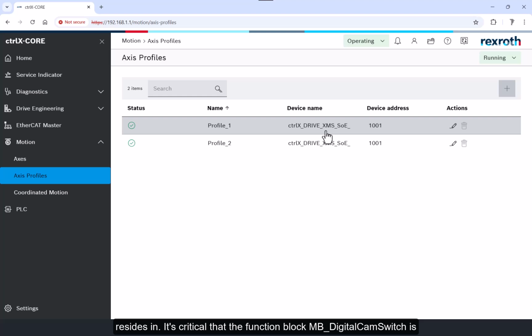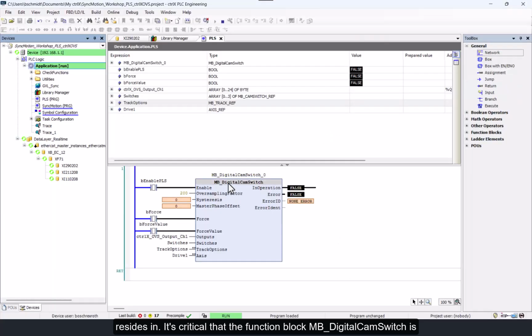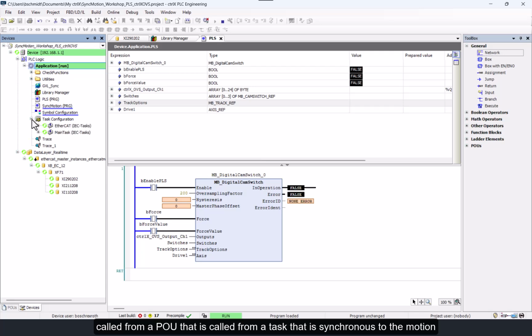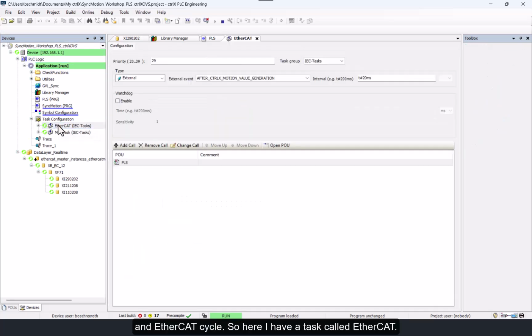It's critical that the function block MB digital cam switch is called from a POU that is called from a task that is synchronous to the motion and EtherCAT cycle. So here I have a task called EtherCAT, and instead of being a standard cyclic trigger, it's an external event trigger that occurs after the ctrlX motion values are calculated each cycle. This task will execute the PLS POU. If we were to run this in a standard cyclic task, even if it's a fast task, we would get inconsistent performance with the timing of the rising and falling edges of the outputs compared to the on and off positions.